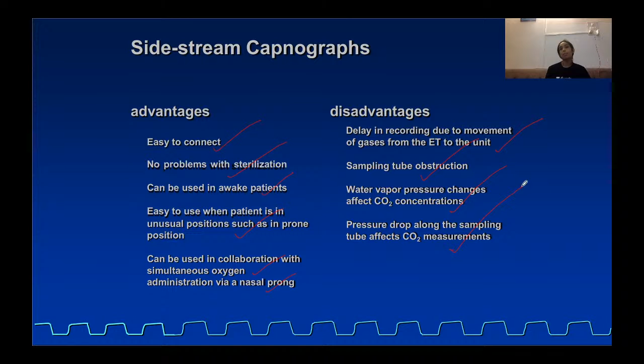Then, water vapor pressure changes affect carbon dioxide concentration. So these analyzers have to be corrected for atmospheric pressure and water vapor pressure, because these cause changes. Then, pressure drop along the sampling tube affects carbon dioxide measurements. So any pressure drop will affect the reading.